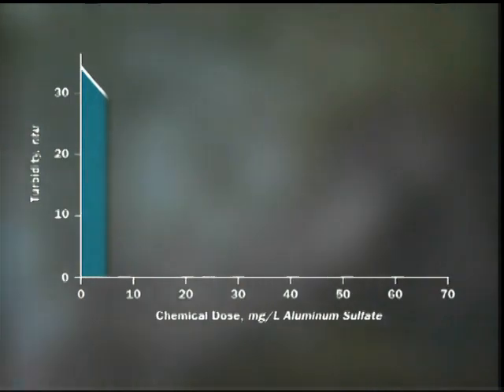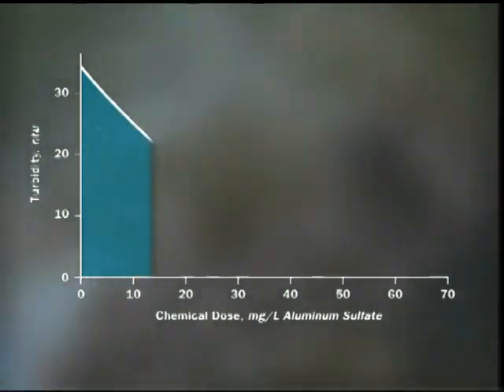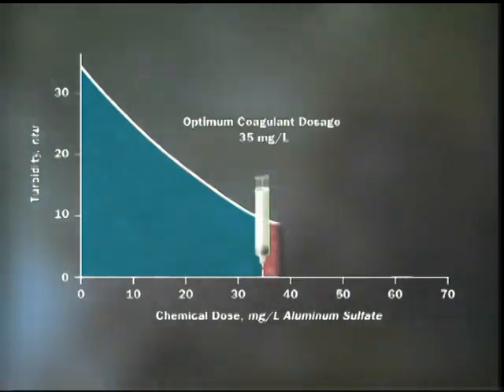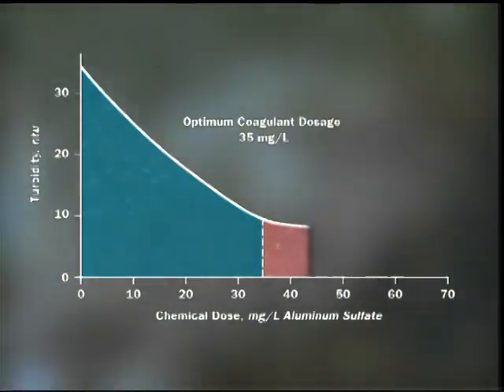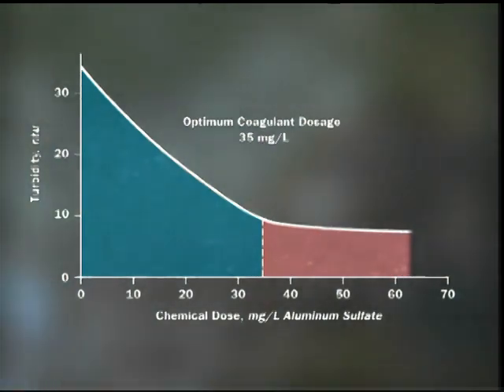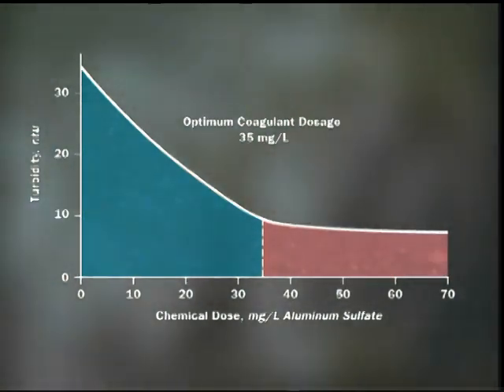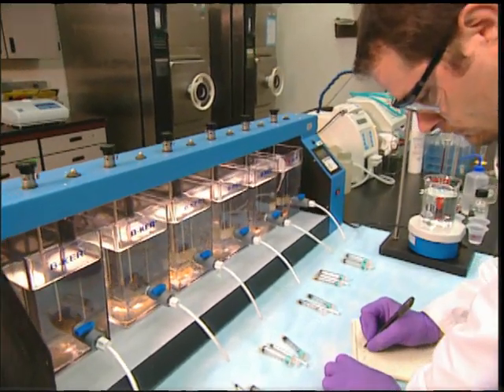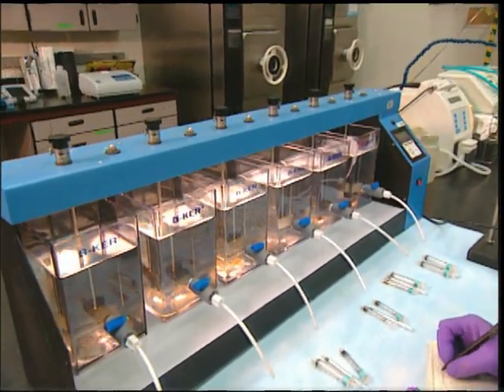Effective particle removal is dependent on the operator applying the right doses of the proper chemicals. At the proper dose, turbidity removal is maximized. Beyond this point, an increased chemical dose yields little additional turbidity removal. Simply adding more and more chemicals and expecting better treatment is not correct — the proper balance must be found. Optimizing treatment is the real point of jar testing.